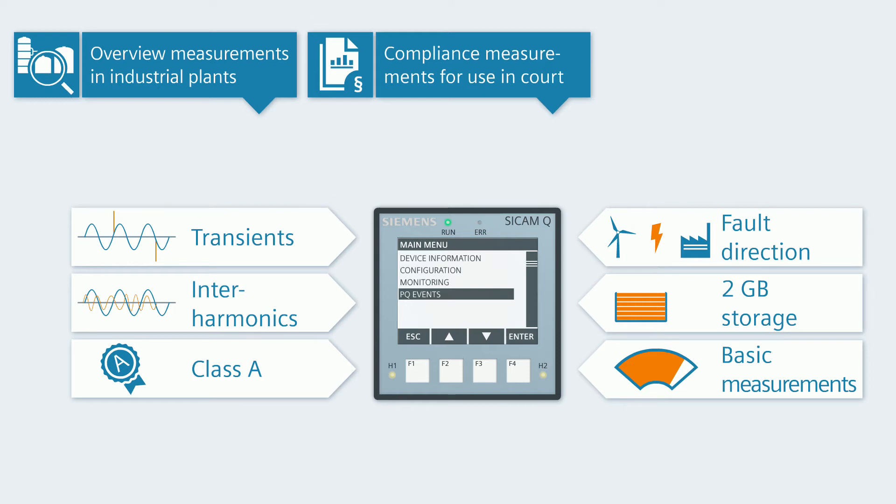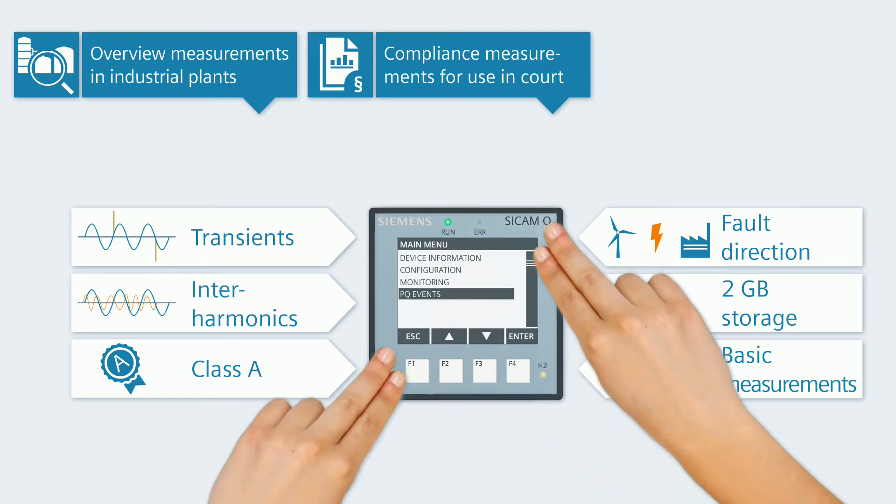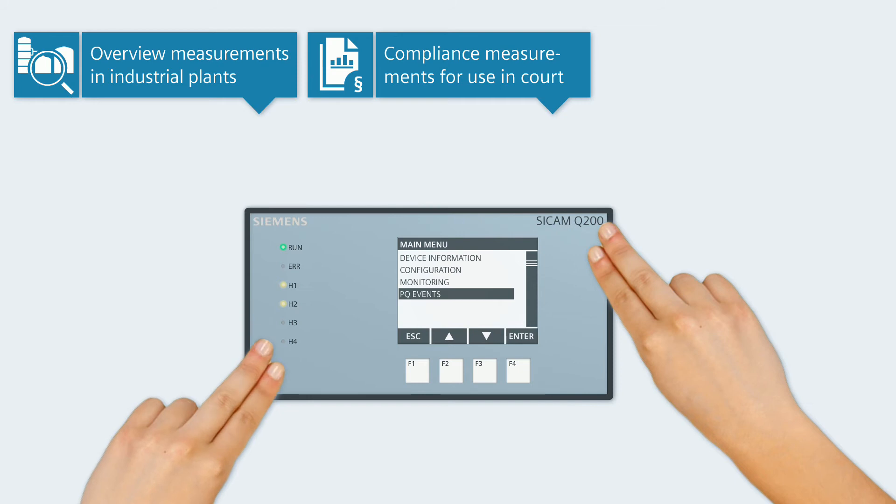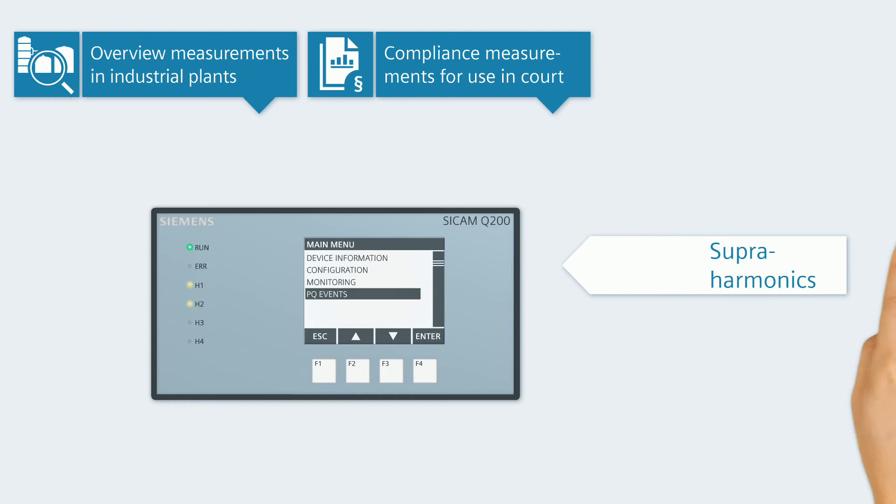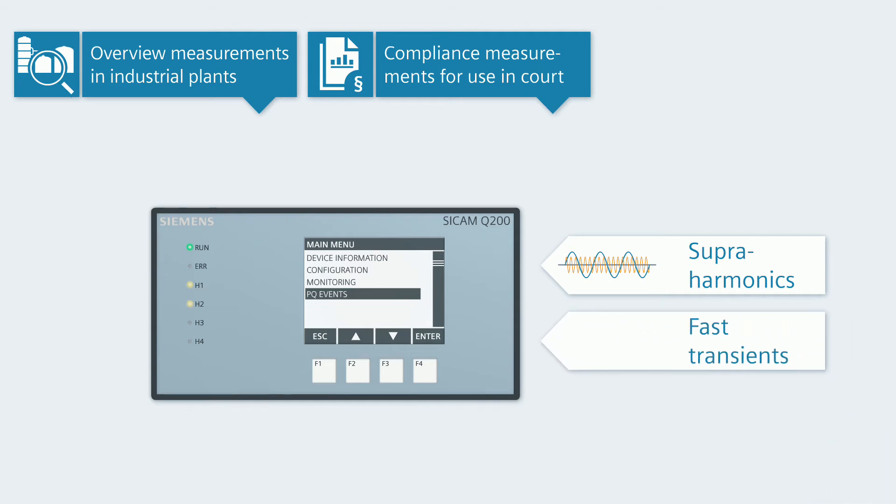The larger multifunctional measuring device SICAM Q200 covers all properties of the two other devices and even tracks down high frequency interferences. SICAM Q200 measures supraharmonics in the range of 2 kHz to 150 kHz. In addition, the device records extremely fast transients up to 6 kV.